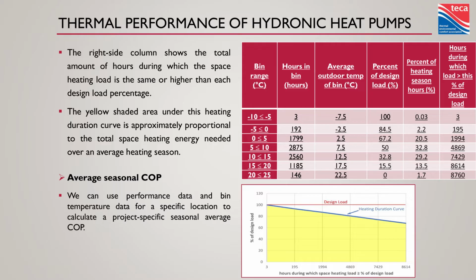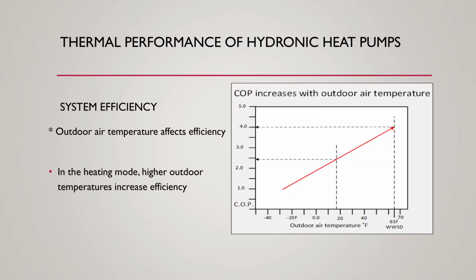Meanwhile, 32% to 67% of the load, these three sections here, represent a large chunk of the heating season. So just remember that when you're selecting your heat pumps. You don't have to find a heat pump that's going to cover 100% of that design load. If you do, you're probably going to end up with a pretty big buffer tank if you did your math right as well. Now, our efficiency goes up as the outdoor air temperature goes up. Great thing, we've got more heat energy there. It also goes up as the leaving water temperature goes down. So if I can heat with lower temperatures, I gain more efficiency with that too.